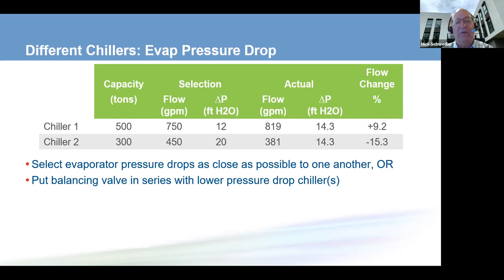And what happens sometimes if this difference is significant is we find we are not able to load this smaller chiller because its flow rate is lower than design. So we can only load it up to 85% capacity. And if the return water temperature to the large chiller is at design conditions, it can't make set point because we have too high a flow rate. It can only produce a certain delta T, and we end up losing our load by 10%.